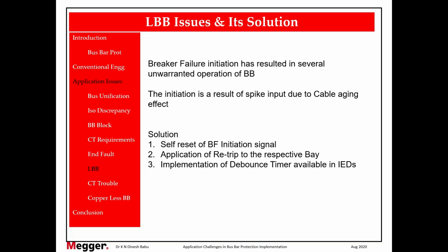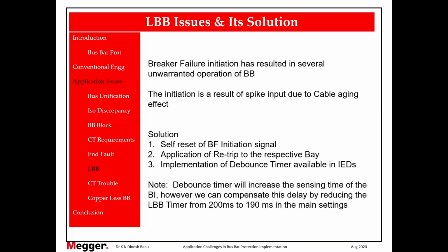Okay. Now there is one question. If I increase the debounce timer, then for a real fault, there will be delayed tripping by that particular duration. Very good question. So the answer is reduce your trip time of LBB. If you are using a debounce timer of 10 milliseconds, instead of configuring 200 milliseconds for LBB, make it 190 milliseconds. The balance 10 milliseconds is compensated in the debounce timer. So the final output is still the same. Your bus bar will be tripped after 200 milliseconds only. So we are not actually challenging any guidelines here. We are compliant to that with advanced sophisticated technology.